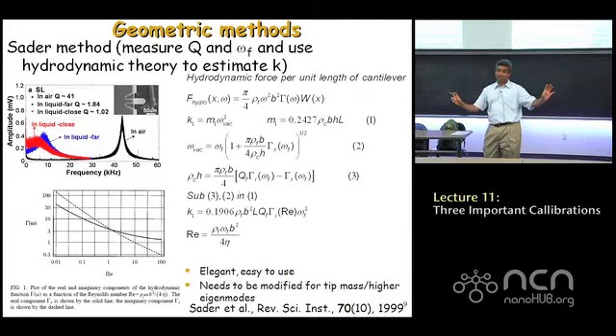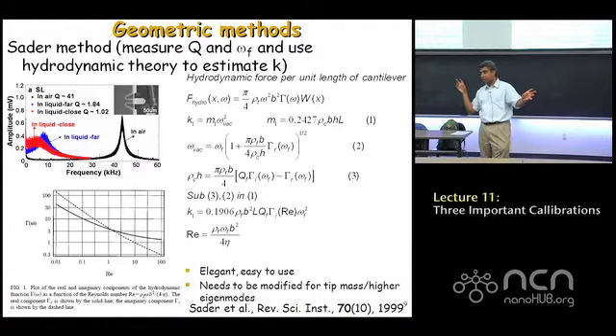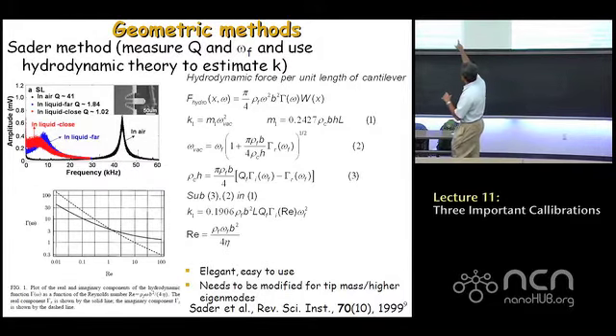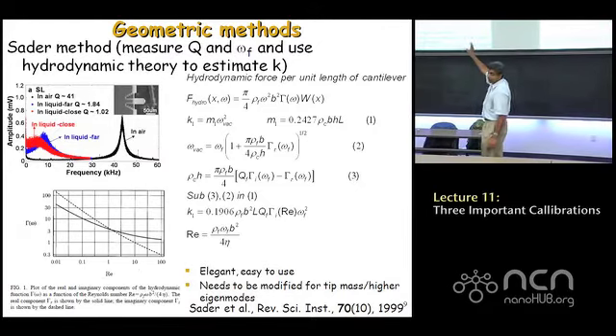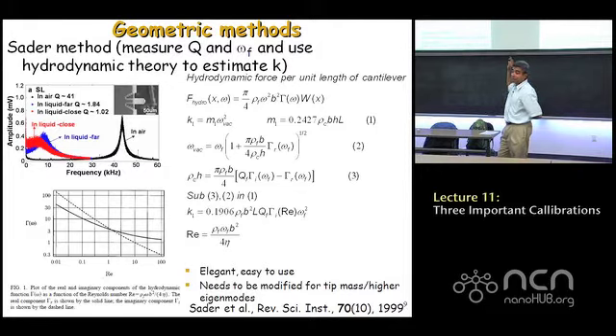So in vacuum, there's no added mass from the fluid, right? There's no fluid effect because it's in vacuum. And you can imagine that this process of trying to connect what the frequency would be in vacuum to what it is in a liquid requires you to use the hydrodynamic functions, right? So in vacuum, you have a certain frequency, but as soon as it's put in air or in any liquid, as it oscillates, now it has to push the surrounding air along with it, right? And so the frequency is going to change. And so this idea is embedded inside equation 2. We can look into Sader's paper for more details, but the idea is this: if you tell me what the frequency is in vacuum, I can predict what the frequency will be in any liquid using equation 2.